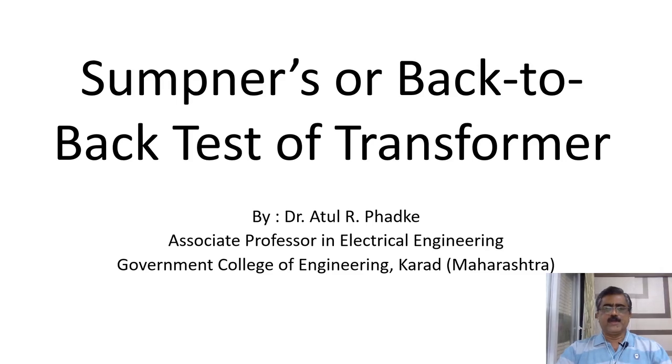In our previous videos, we have studied testing of transformer by direct loading and by OC and SC tests. However, these methods are not suitable to determine the temperature rise characteristics of transformer. In practice, it is very important to check whether the temperature rise of transformer is within permissible limits or not. This can be done by conducting Sumpner's or back-to-back test, which we will study in this video.